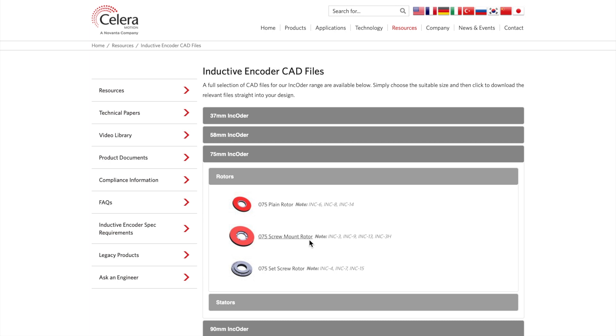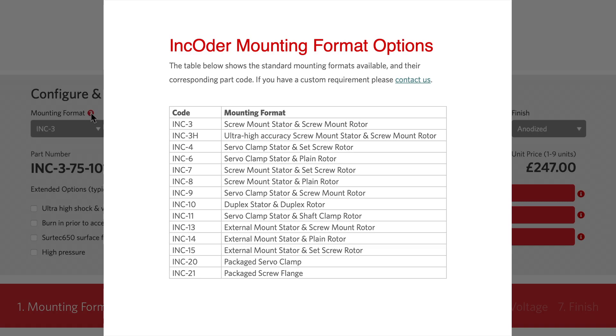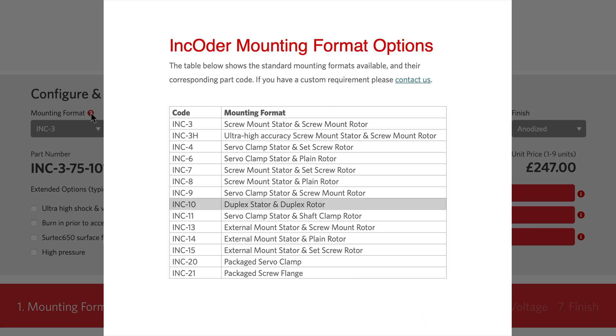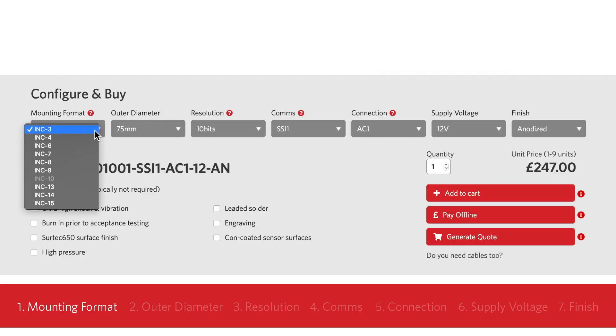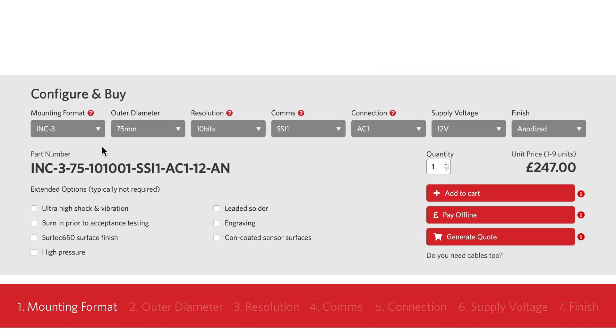For example, you can have a screw mount stator with a set screw rotor, and this will be referred to as INC 7. INC 10 refers to a duplex arrangement — two encoders in a single housing — mostly used for safety related applications where there's a need for electrical redundancy. In our example we'll pick the most common selection, INC 3, which is screw mount stator and screw mount rotor.